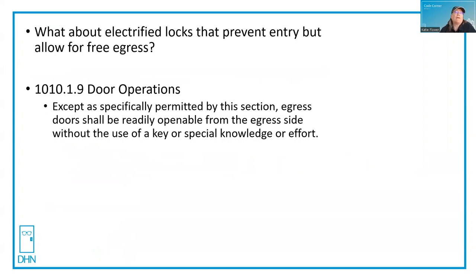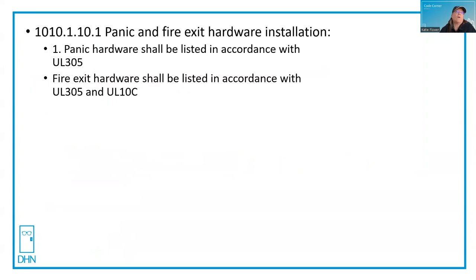Another example of a reference standard is under panic hardware and fire exit hardware, Section 1010.1.10.1. Panic hardware shall be listed in accordance with UL 305, whereas fire exit hardware shall be listed in accordance with UL 305 for panic as well as UL 10C, which is the test standard for fire doors. You don't find UL 305 referenced under the lock set section — if an AHJ asked you for a cylindrical lock listed UL 305, you wouldn't find anybody that makes it, because UL 305 is the standard for panic hardware. So unless a standard is referenced by the code, it does not apply.